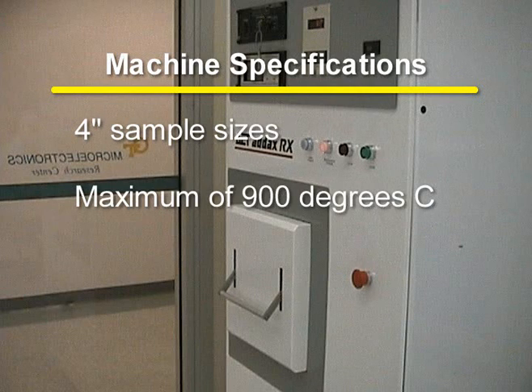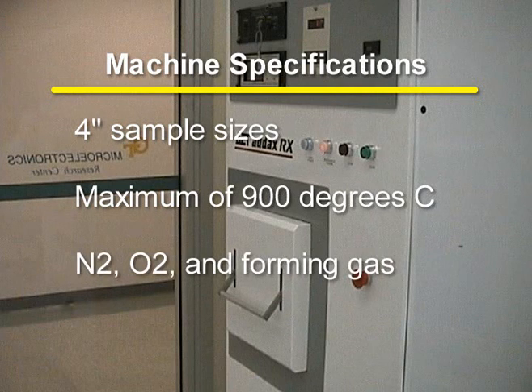The lamps can heat a sample to a maximum of 900 degrees Celsius. If this temperature is exceeded, then the cooling lines connected to the lamp housing will burst. The gases used in this system are nitrogen, oxygen, and forming gas.